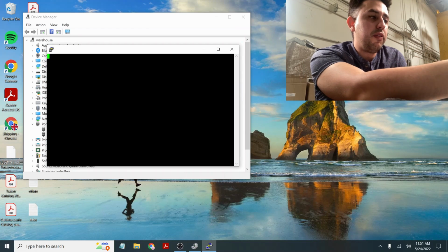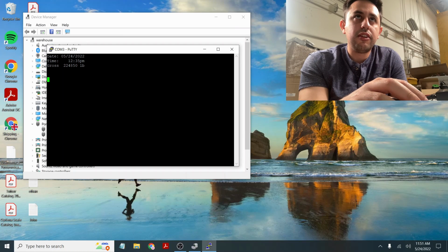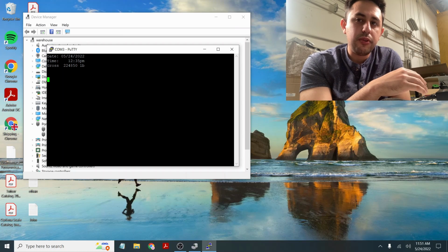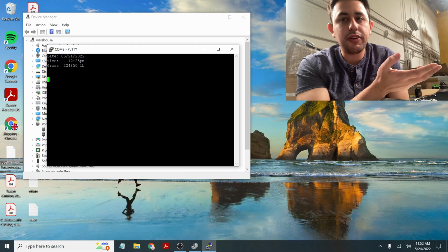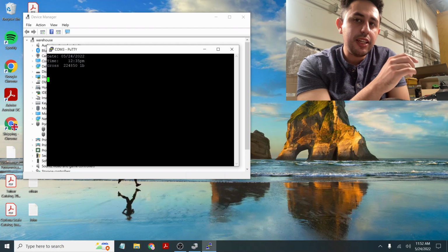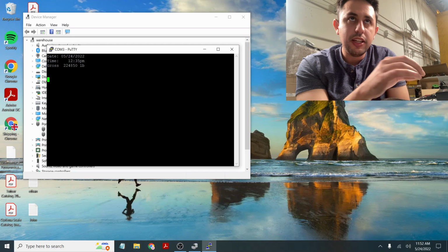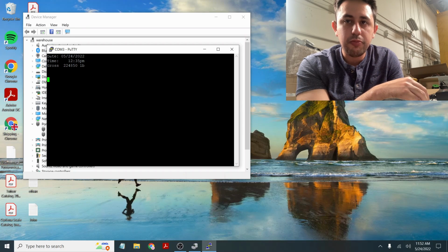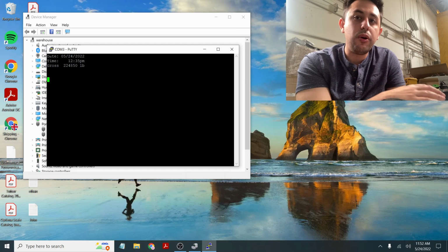See, it's waiting for something, no output. If I do capital P, you can see it prints out the date, time, and gross. If you look on the label, you'll see it has that date, time, and gross. It also added the tare and net in this particular example. If you press capital P and you don't see this, if you see something like 315 space PT, then it will not work with the software.